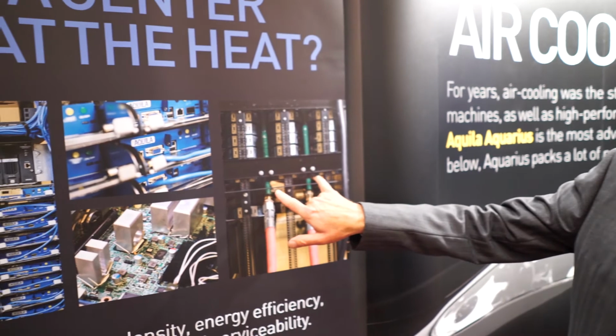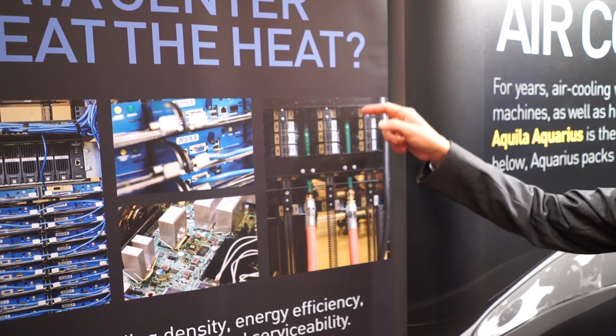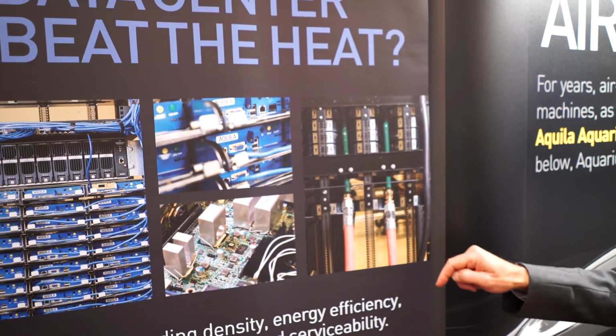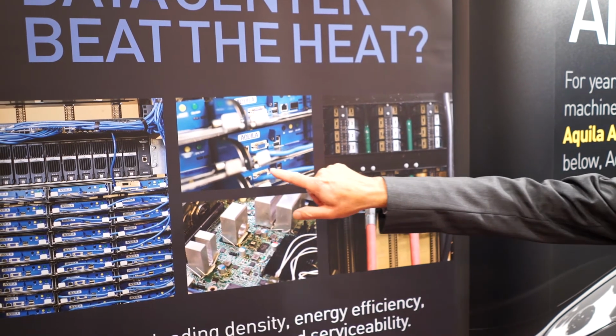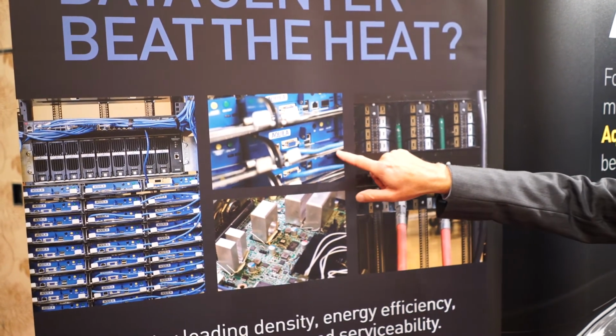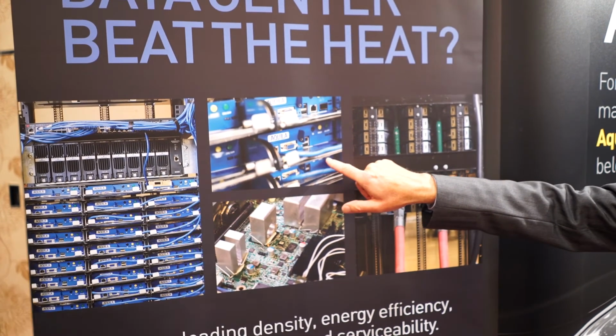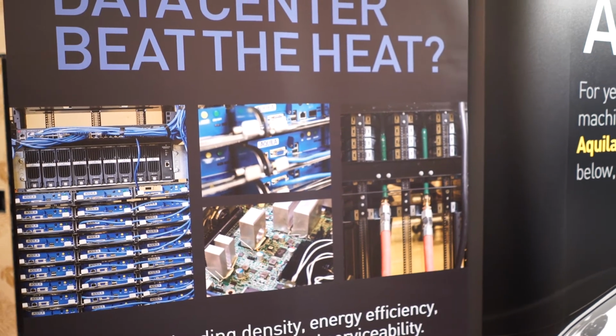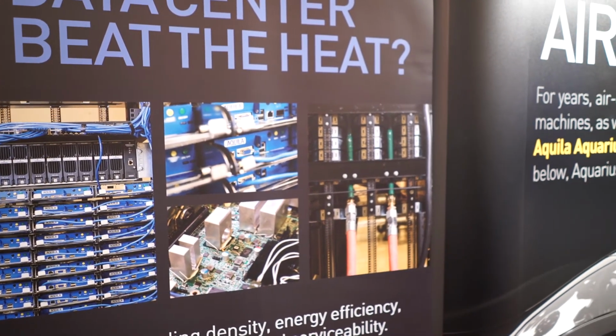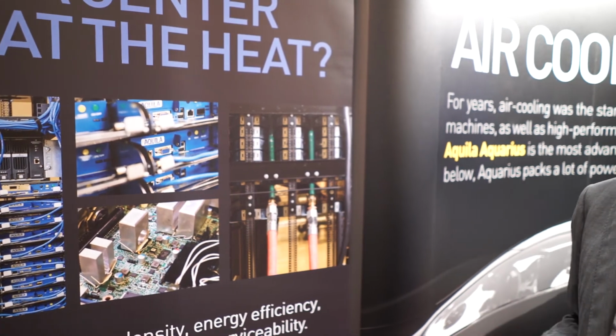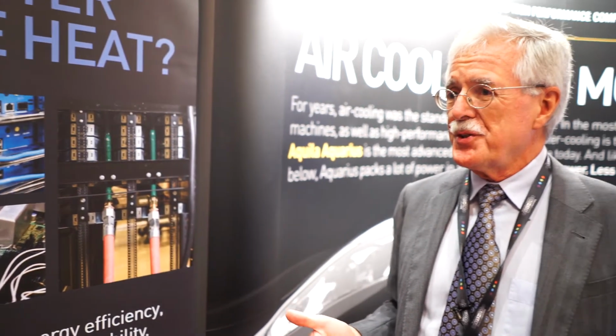Yes, so essentially we've just got 2 pipes coming in, and then there are manifolds with tiny little stubs on them that connect to the cold plates, which you can just see here. So that's a cold metal plate? Yes. And no liquid gets near the electronics? No, it's all contained within the plate. It's a stainless steel plate, which doesn't rust, so it's not going to wear out and drop water on your system.